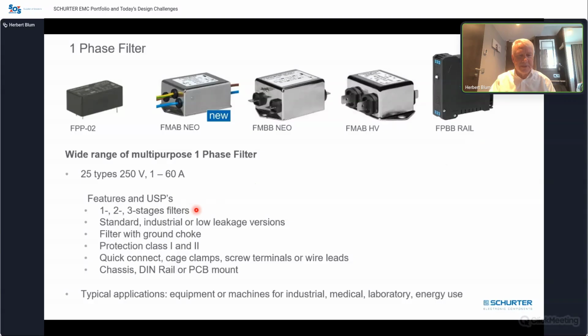It's a bit the same here - different types, different dimensions. You have single stage, double stage, triple stage filters, standard or low leakage current filters. We're also one of the only ones having single phase filters with an integrated ground choke, same topic as I explained for the power entry modules with filters. We're the only one having protection class 2 single phase filters, especially made for medical applications where protection class 2 is required, for example according to standards in home care equipment or in ambulances.